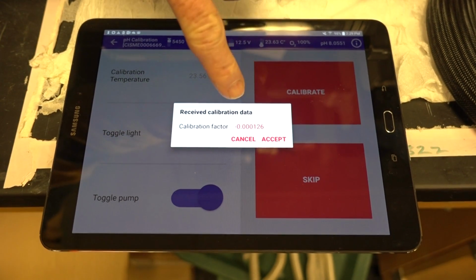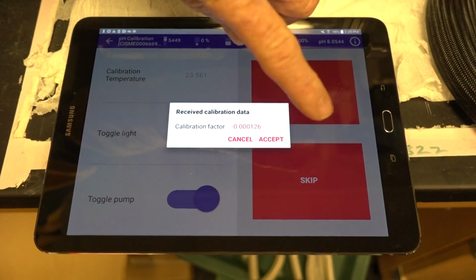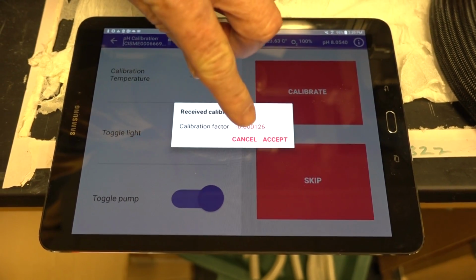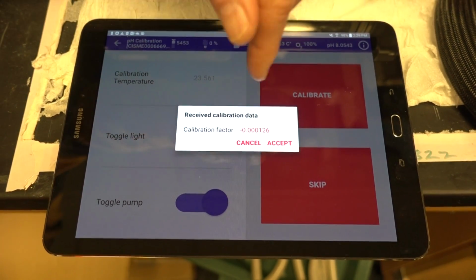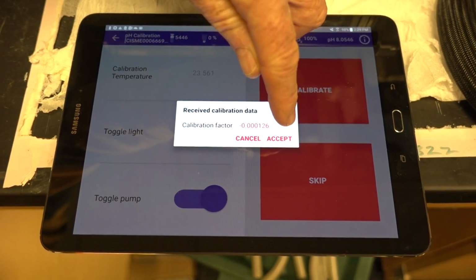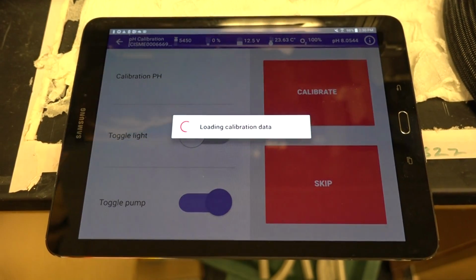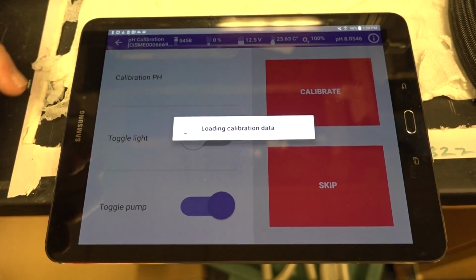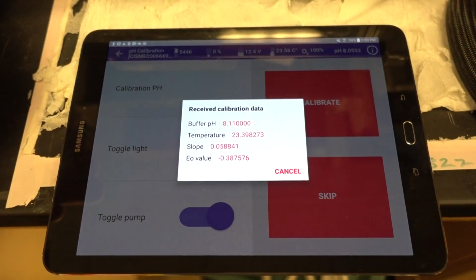And that produces the new calibration factor. If we accept this, it will be written into memory. If we hit cancel, it will reject it and use our previous calibration factor. So I'm going to accept. And now we'll move to the pH calibration step.